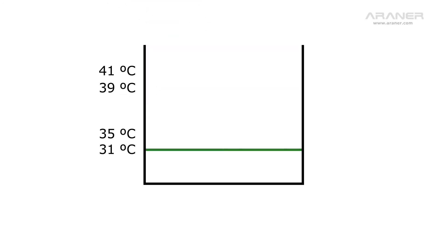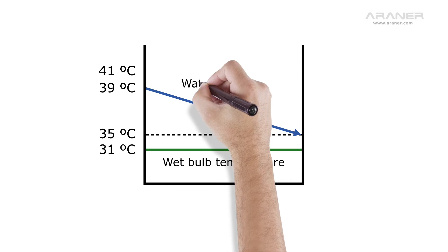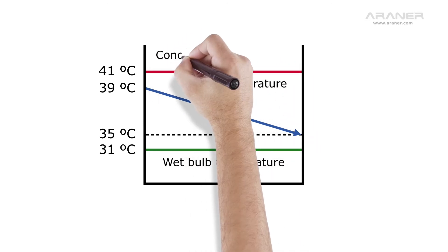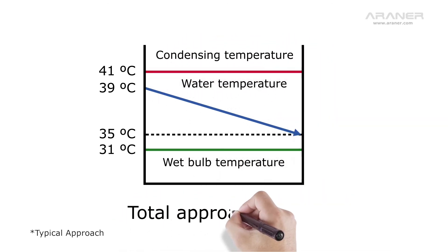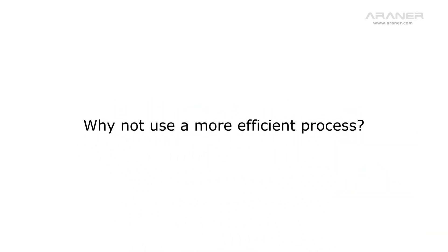If the ambient wet bulb temperature is 31 degrees Celsius and we are using a cooling tower with an approach of 4, then our cooling water will be 35. This water will be heated up to 39 in the condenser, so the condensing temperature has to be 41, ending up in a total approach of 10.